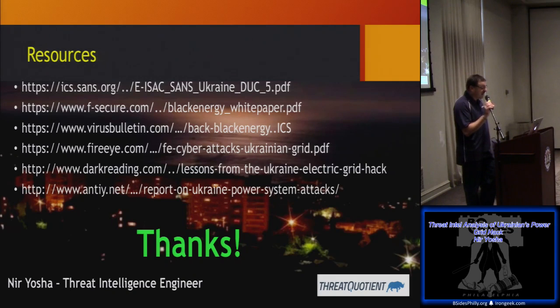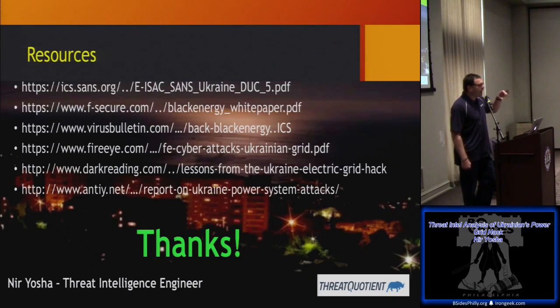Okay, so the question was, how do we approach serial network based as opposed to IP based? That's a good question. What is happening today is there's a trend where you are encapsulating those legacy serial protocols and starting to put them over IP. There are certain additional security components that you need to add with those, because you cannot keep your network with the same security measures after you move from serial based to IP. When you add IP, you also add potential additional vectors to attack the SCADA network. And so there are specific products in the market aimed specifically at security issues related to what they call SCADA over IP.